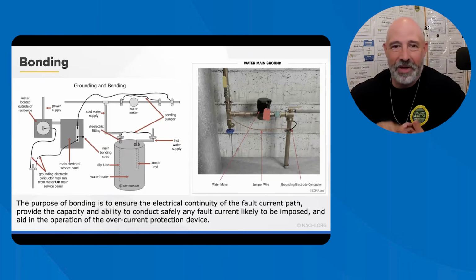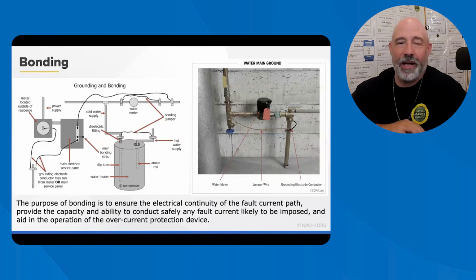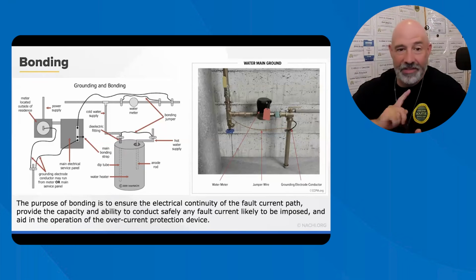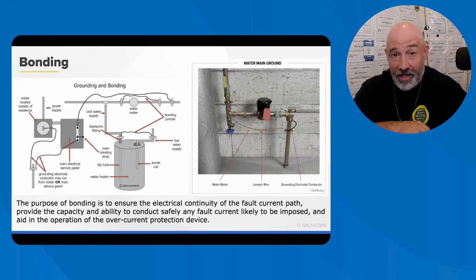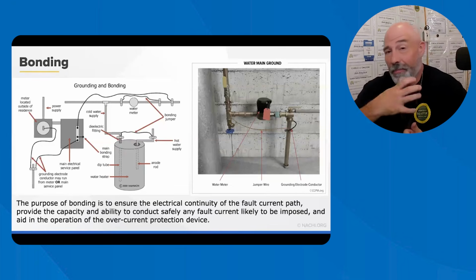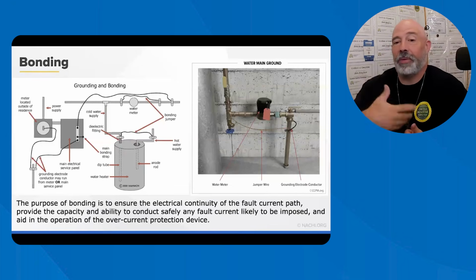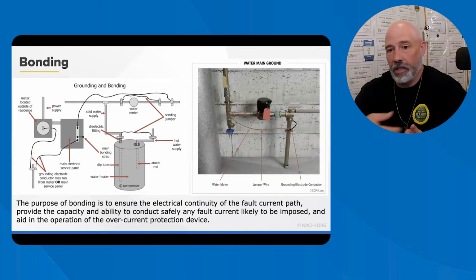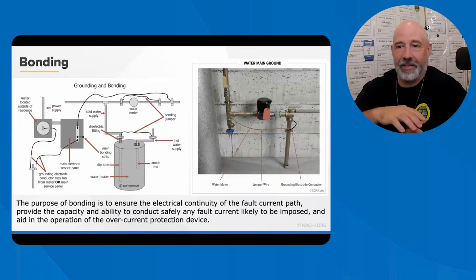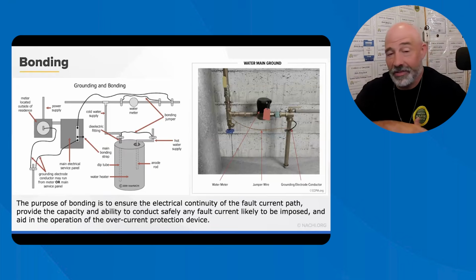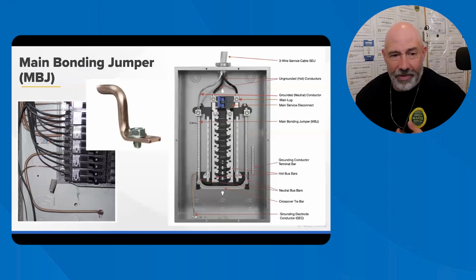Other metal components that should be bonded include the water piping, the gas piping, the water heaters, the CSST piping, electrical enclosures, the raceways, telephone cable systems, things like that. Bonding helps ensure that if metal components become energized, they have a place to go, and the breaker trips instead of the metal remaining energized and causing someone to get shocked. And if you get shocked, it doesn't feel the best. I'm just letting you know.